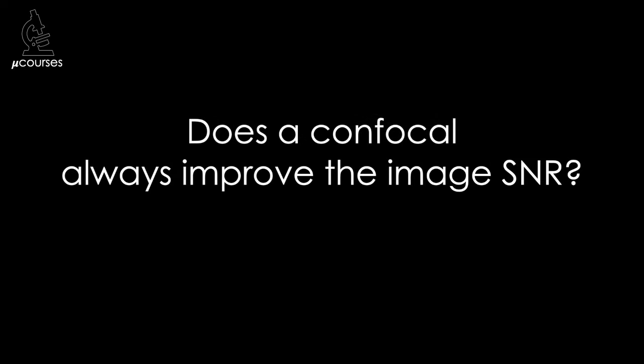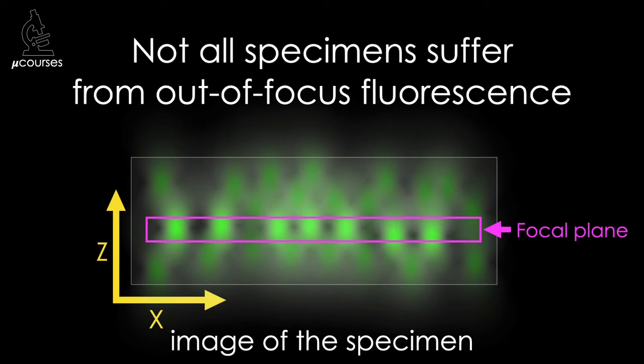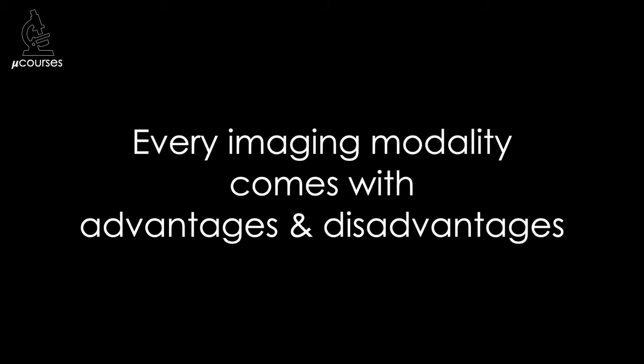But does a confocal microscope always improve the image signal-to-noise ratio? I'm afraid it's not that simple. The major advantage of confocal is reduction of out-of-focus fluorescence. If your images aren't degraded by out-of-focus fluorescence — because there's no fluorophore outside the focal plane or your specimen is thin — you won't see that advantage. The unfortunate reality is that every imaging modality comes with both advantages and disadvantages, so if you aren't getting the advantages, you're only getting the disadvantages. Navigating the advantages and disadvantages of confocal will be covered in another microcourse.